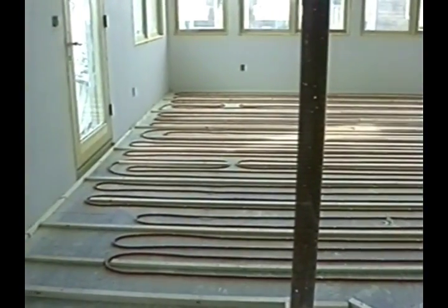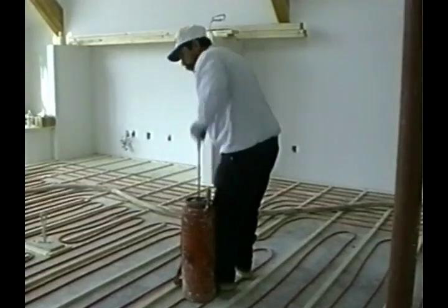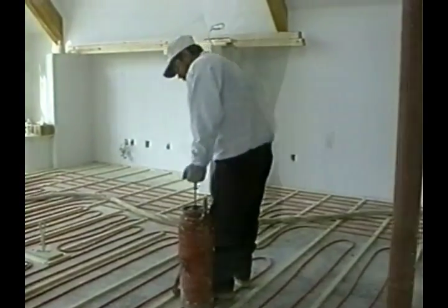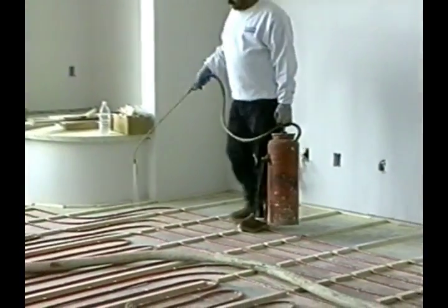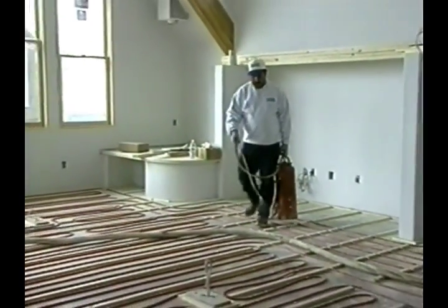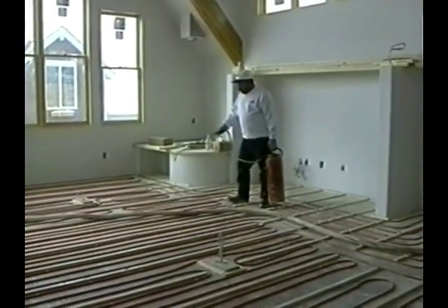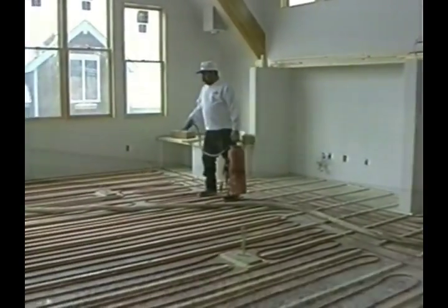Stapledown applications require the addition of a thermal mass. Thermofloor is a lightweight gypsum-based cement that encapsulates the tubing. Before pouring Thermofloor, the subfloor needs to be cleaned and a primer adhesive applied. To account for the change in floor heights caused by the application of Thermofloor, use a double sill plate.